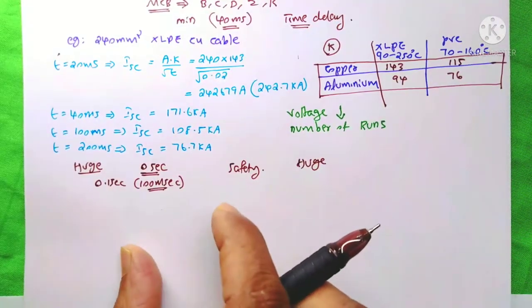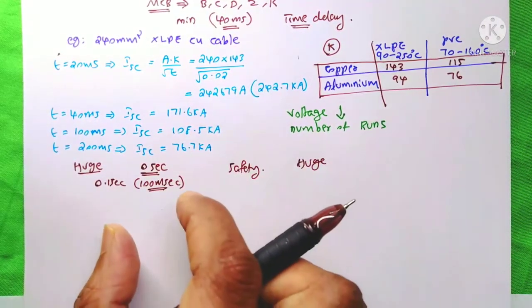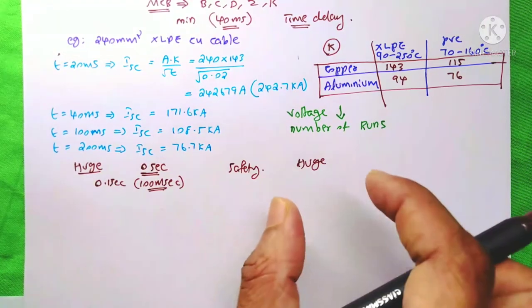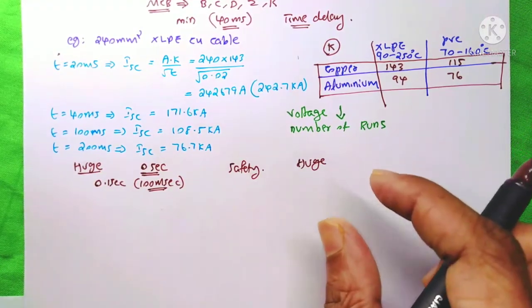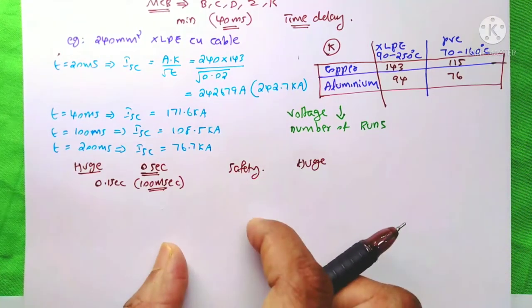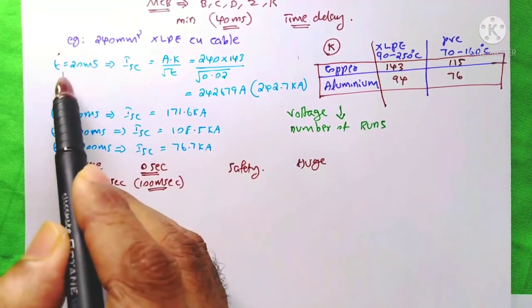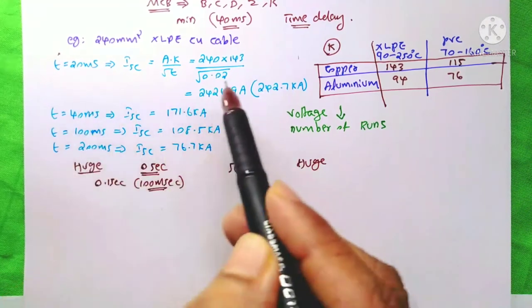We need to compare that short circuit capacity of the cable with the system short circuit that is going to happen when a short circuit appears on the system. When you take a minimum tripping time, the short circuit capacity is 242 kA.